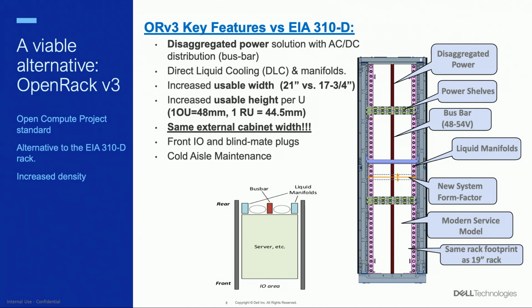So the key tenets of the Open Rack v3 specification are disaggregated power - basically, we no longer have PSUs within each rack, but power shelves serving the entire rack with a bus bar distributing power across the back of the chassis to all the servers. We also have an integrated liquid cooling solution, with manifolds in the back where servers connect directly through blind mate connections, a much more efficient way of connecting to the liquid cooling system, without a lot of cables hanging in the back.